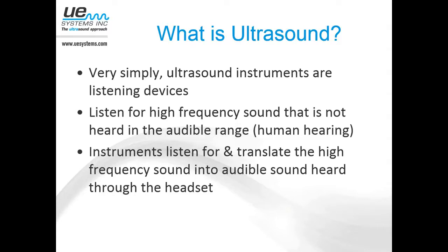And the third thing it does when it translates that high frequency sound is, with some of our instruments, it gives us the ability to record those sounds. That gives us the ability to do some further analysis, which I'll talk about in a few minutes. But essentially, it's a high frequency listening device. It only hears sound, it doesn't emit anything, and it lets us listen to a whole range that we can't hear with our ears.